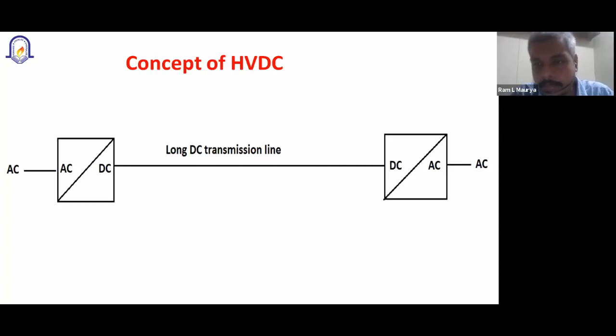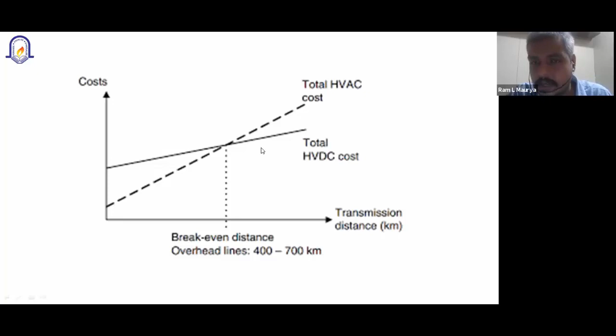We have always learned that an AC system is economical as compared to DC transmission. But we have to understand that after 400 to 600 kilometers, the cost of AC transmission increases. If you are below 400 to 600 kilometers, AC transmission is okay. But above that, the losses increase, there are line reactances, and many such hindrances. So we go for HVDC. As you can see here, after this break-even point, the cost of AC keeps increasing, because the initial cost of an HVDC converter station is high. That's why at low distances we are not using HVDC transmission.